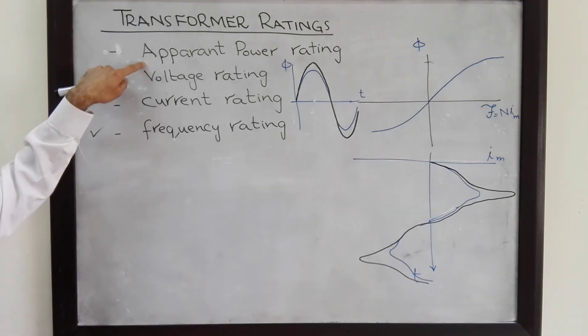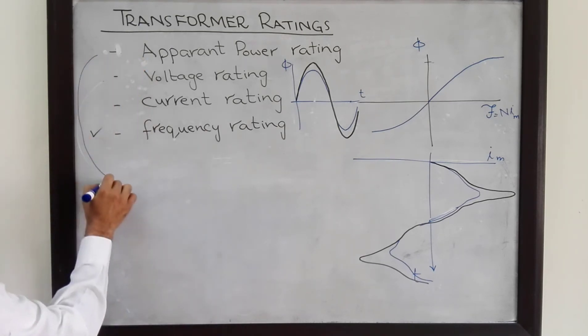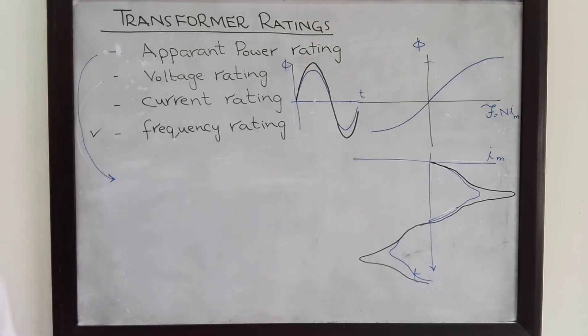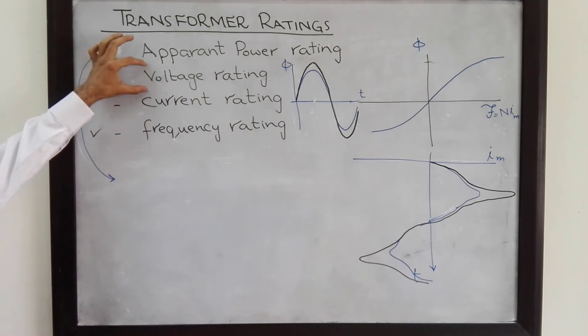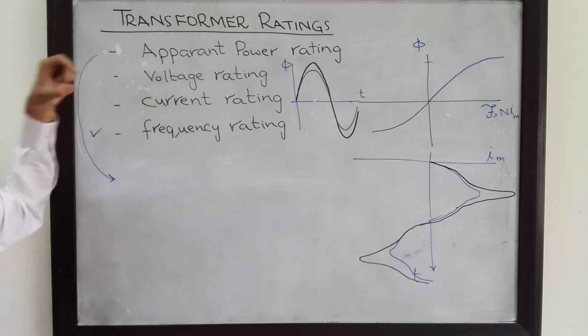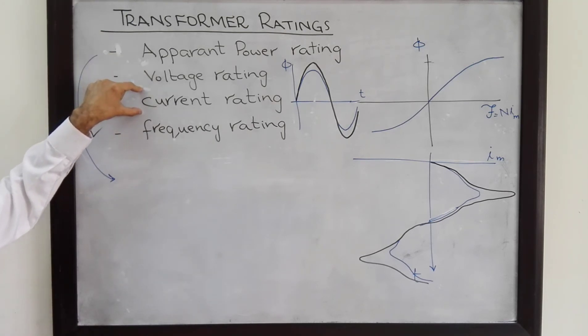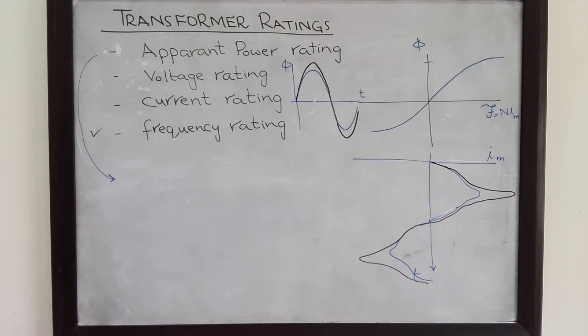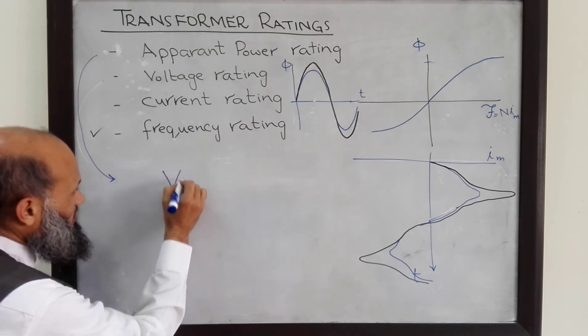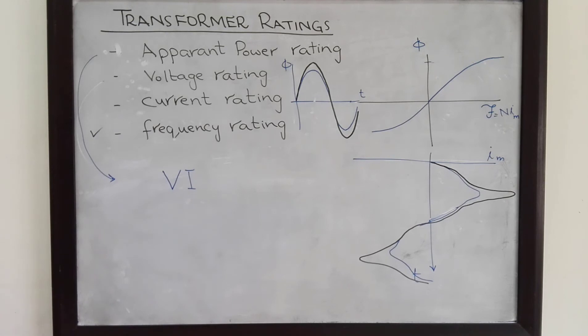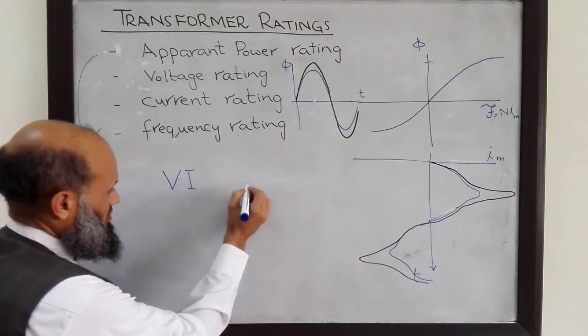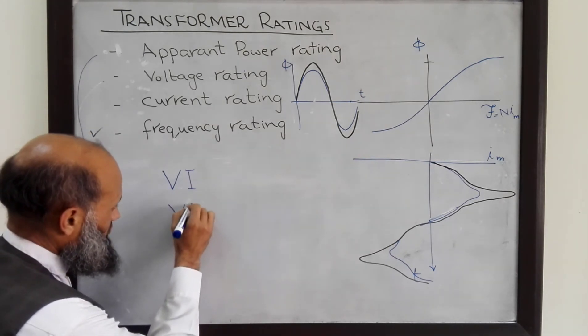Another very important rating of transformers is the apparent power rating. Power ratings of electrical machines are always provided in apparent power. There is a maximum voltage that can be applied to the transformer and a maximum current that can flow through the transformer. Therefore, there is a limit on their product, V×I, and that product is the apparent power rating for a transformer — this is the volt-ampere rating.